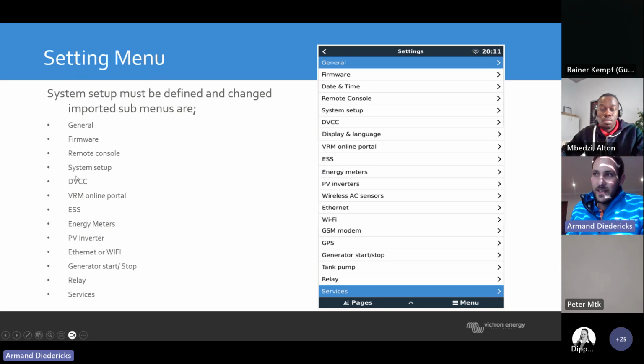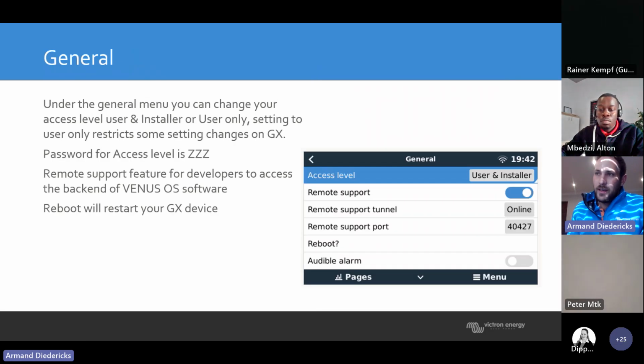There's just a couple of settings that you set up if you run ESS and if you want to do remote support. Under the general menu, you can change your access level, user and installer, or user only, to restrict some settings changes on the GX. So obviously we all have clients that fiddle with the system. Then everything bombs out, then he phones you and blames the system, but he never told you he fiddled around with settings. So what you can do, you can set the access level and actually create a password. So they'll only have viewer rights that way. They won't be able to change any settings.